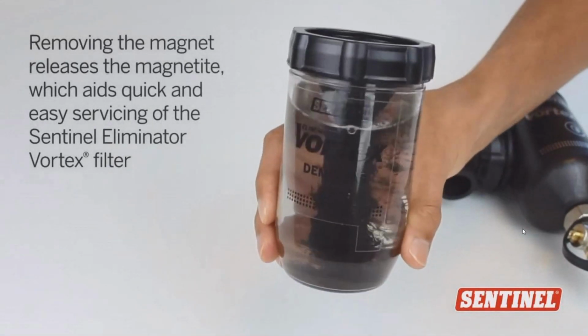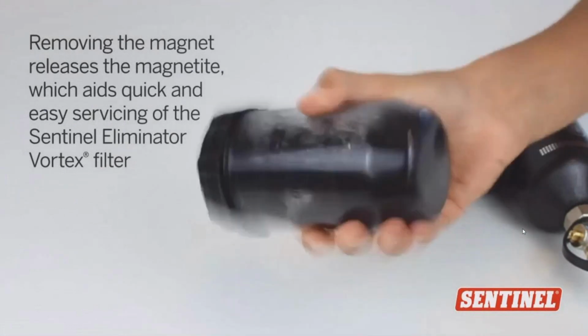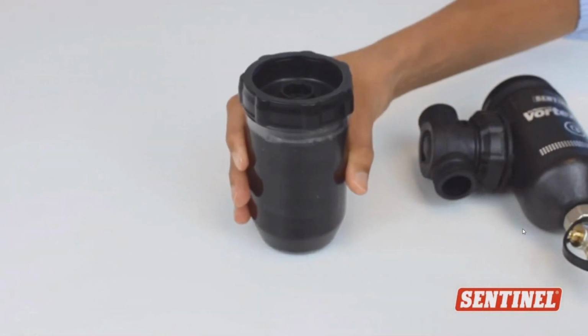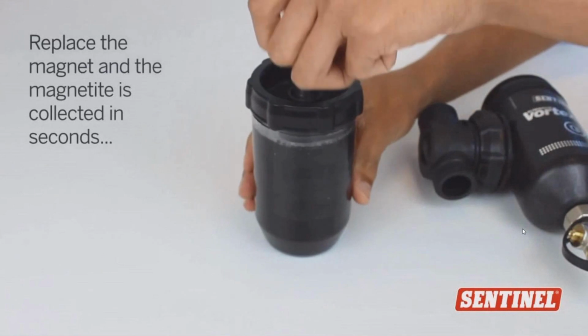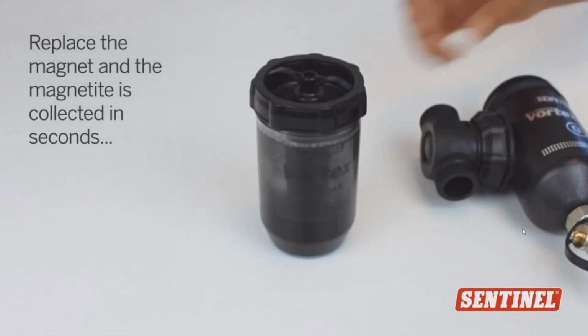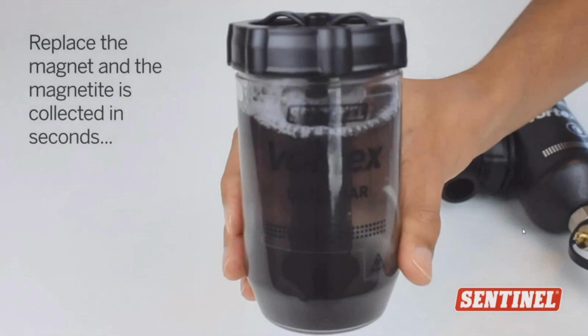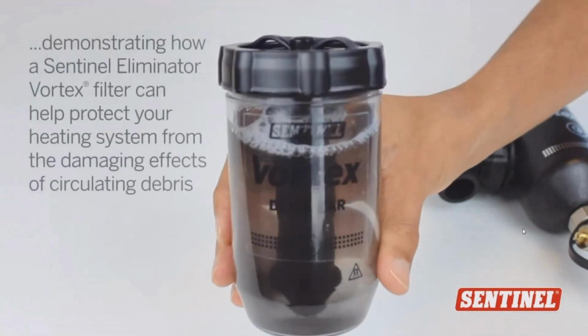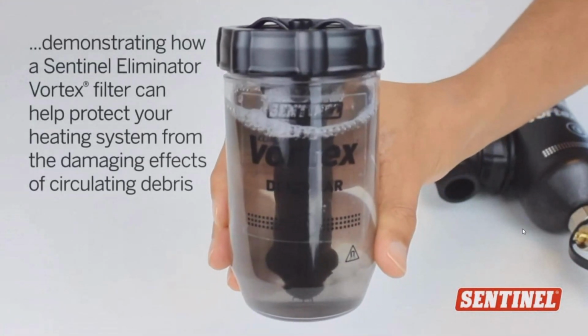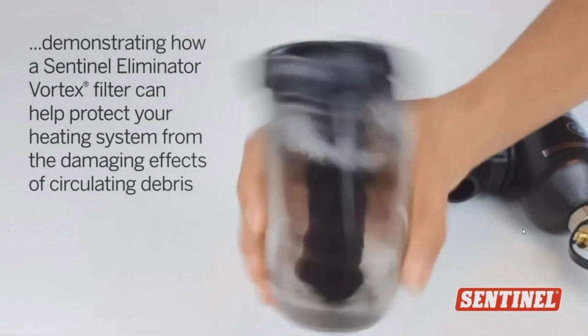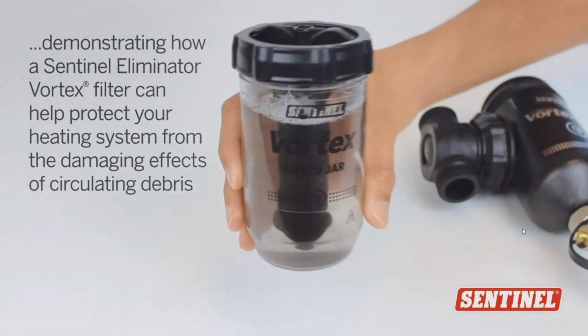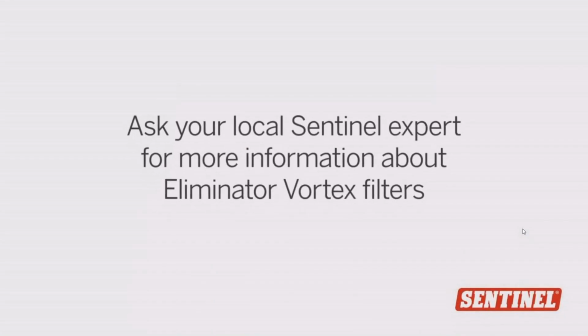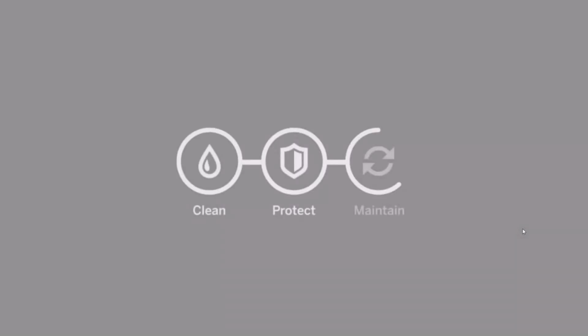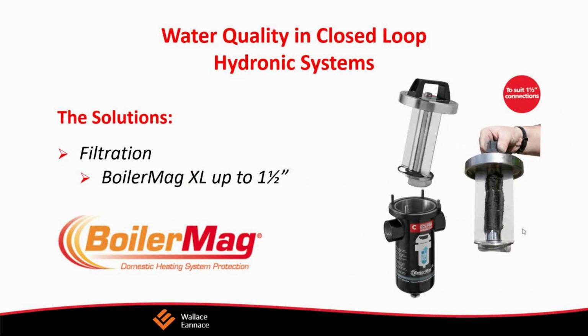I suppose any of you have ever done a radiant heat installation with clear tubing. You install, and very shortly thereafter, you find that there's a variety of dark black streaks inside and in the bottom of the tubing, and that's magnetite. And magnetite is pretty much in all hydronic systems. There are too many iron components to prevent it from leaching into the water. And Lochinvar wants a field supplied magnetic separator on the return line as close as practicable, per the magnetic separator's instructions. They require that.